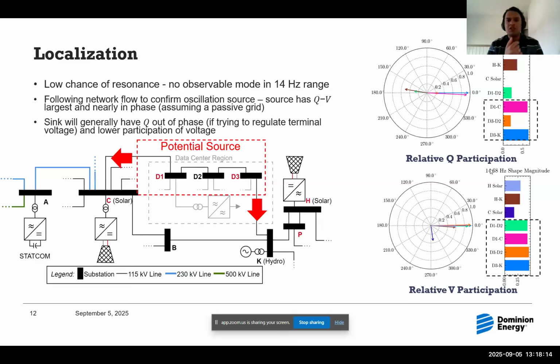And localizing for this case is relatively easier. First of all, it's in the 14 hertz range. There is no local dynamics to resonate with this 14 hertz, at least not that we know of from ambient conditions. But also, what we do is we chase the volt and the var relative participation of different parts of the network to localize the oscillation. So what you'll notice here is that for the oscillation shape or mode shape, the top one is for reactive power participation of different lines in this part of the system, and the bottom one is the voltage magnitude participation.